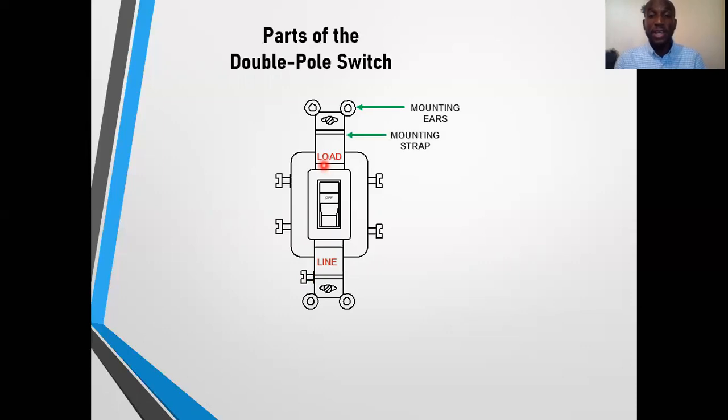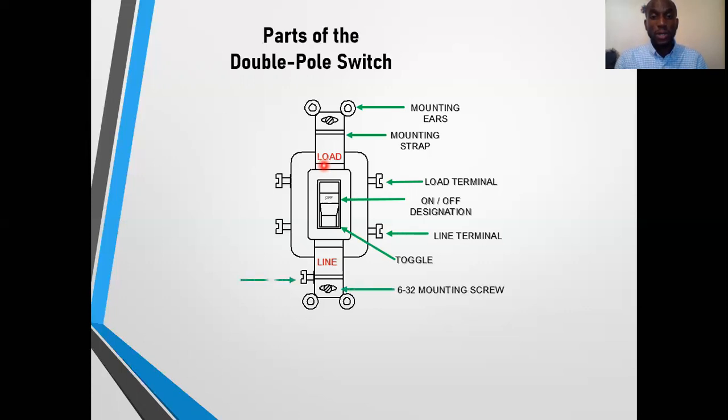As said before, this double-pole switch is similar to the single-pole switch only that it has four terminals. Parts are similar: the mounting ears, the mounting strap, we have a load terminal, we have the on or off designation, we have a line terminal, we have the toggle, we have the 6-32 mounting screws, there's also the grounding terminal, then you have the balancing line terminal, and to complete it all we have the balancing load terminal. As you can see, both load terminals are across from each other. Both line terminals are across from each other.